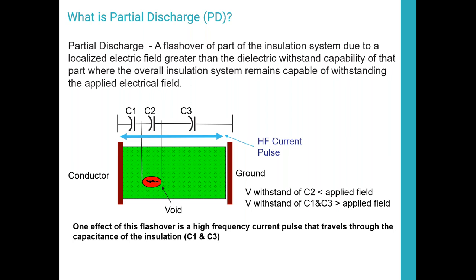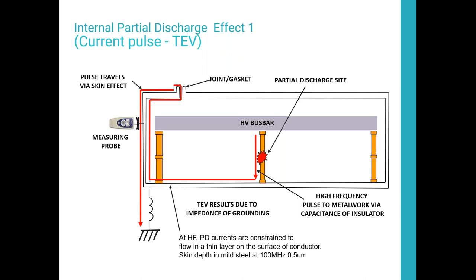That's correct. So if you assume your TEV test set is looking at voltage, you have one lead, which is a capacitive plate, usually in the front of the instrument that's held against the device you're testing, whether it's the front of switchgear or the sheath of cable, but you're capacitively coupling into that gear itself. And then the other lead is typically this equipment has a conductive body, and the person holding the instrument forms a capacitive sink, much like an AM radio has, so it's a voltage device, but still has one lead. So the voltmeter that is the TEV probe consists of a capacitive clamp held up against the equipment and a conductive body that is, the human is forming the capacitive sink for the radio detection.